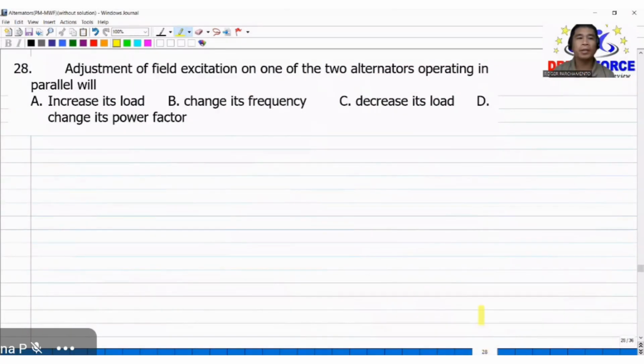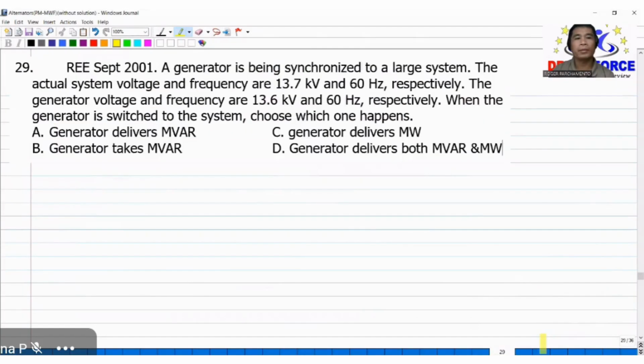So next, number 28, the adjustment of field excitation on one of the two alternators operating in parallel will change its power factor. So number 29, generator is being synchronized to a large system. The actual system voltage and frequency are 13.7 kilovolt and 60 Hz respectively. The generator voltage and frequency are 13.6 kilovolts and 60 Hz respectively. When the generator is switched to the system, choose which one happens.